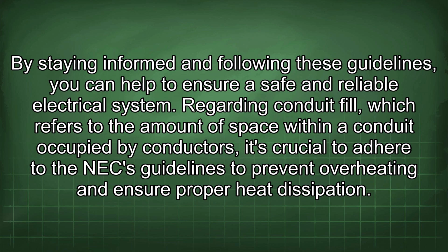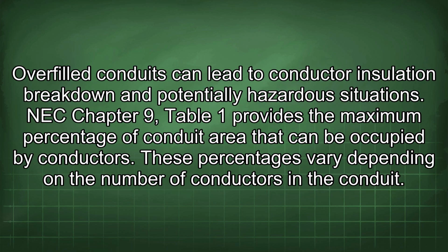Regarding conduit fill, which refers to the amount of space within a conduit occupied by conductors, it's crucial to adhere to the NEC guidelines to prevent overheating and ensure proper heat dissipation. Overfilled conduits can lead to conductor insulation breakdown and potentially hazardous situations. NEC Chapter 9, Table 1 provides the maximum percentage of conduit area that can be occupied by conductors. These percentages vary depending on the number of conductors in the conduit.